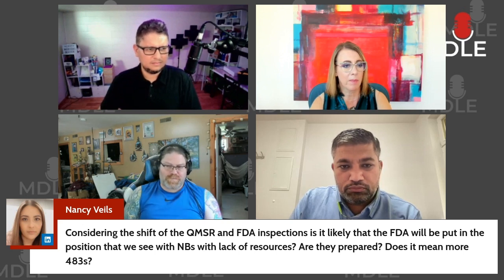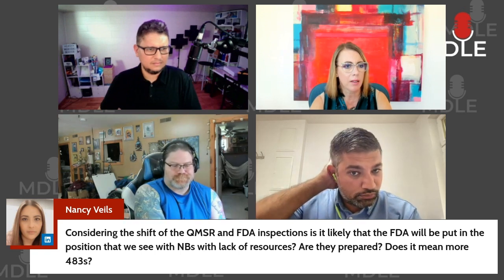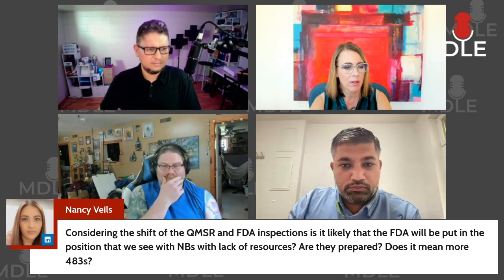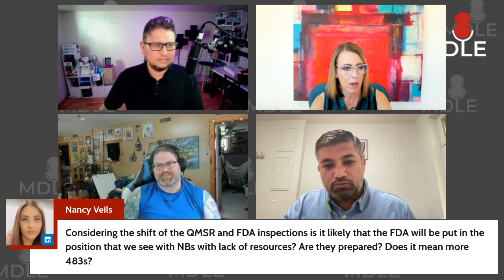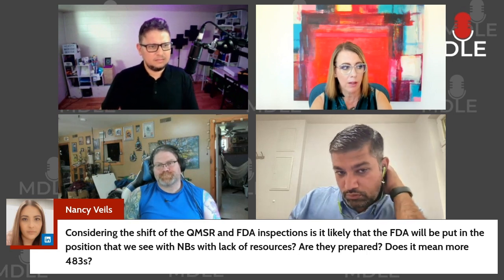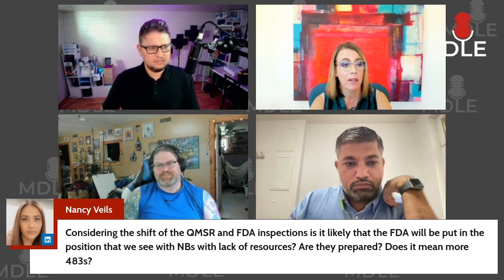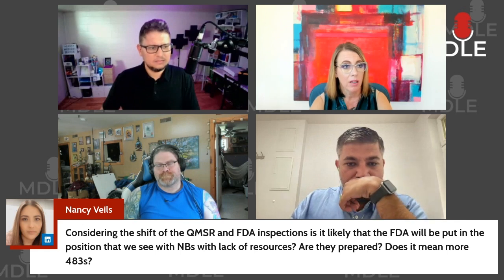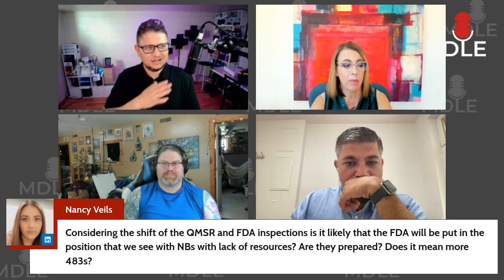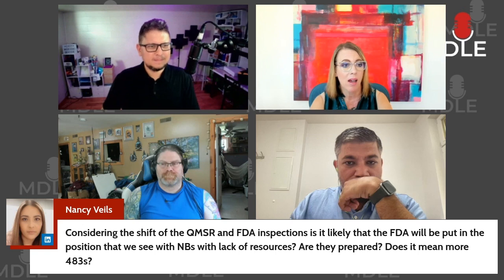If it goes well, it's like 1 to 2 days for a small manufacturer. But to Rob's point, if they do have to follow a checklist and they have to write something in for every box, you should expect that the FDA inspection is going to take just as long as an MDSAP or ISO 13485 audit.